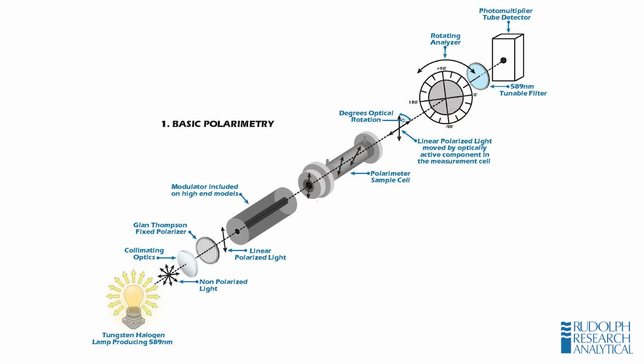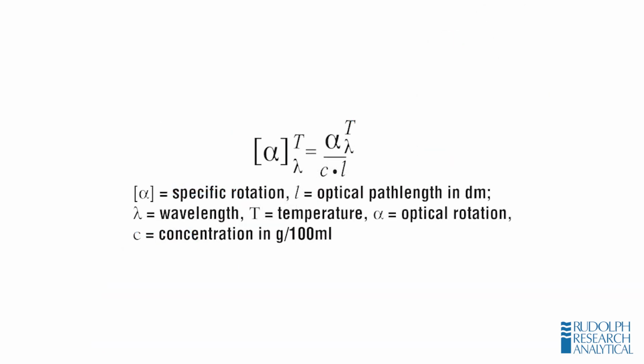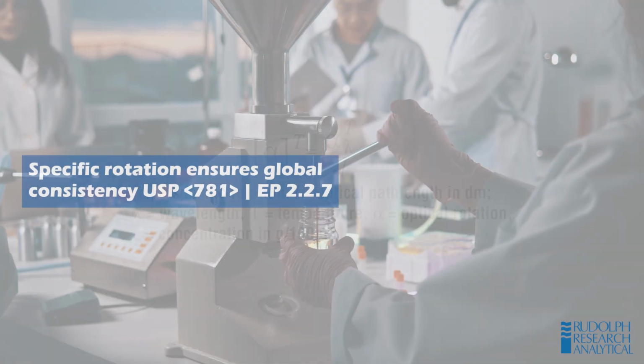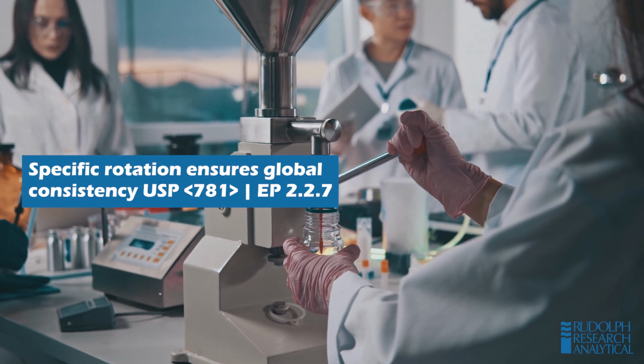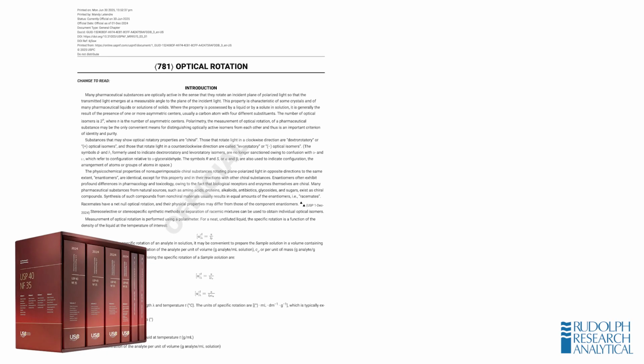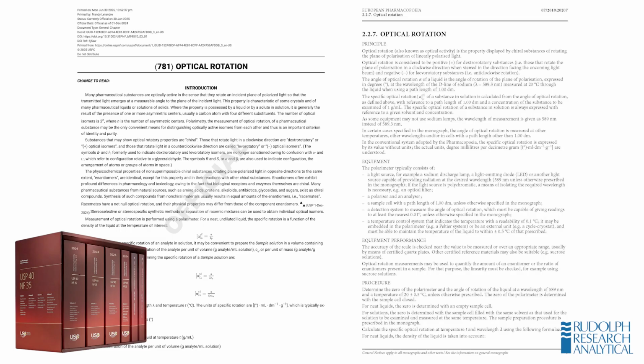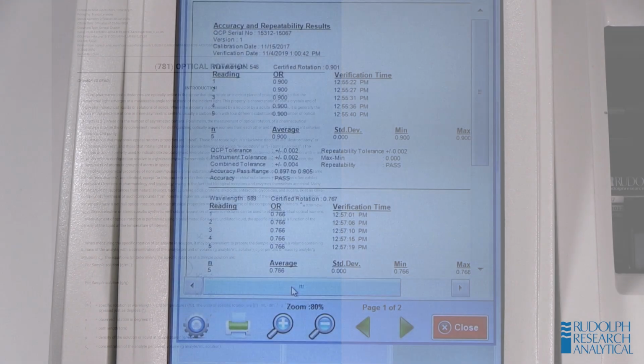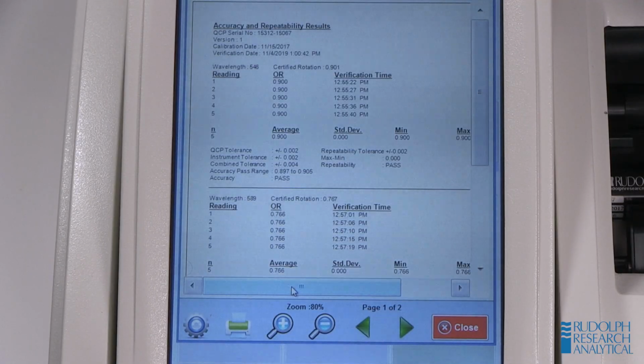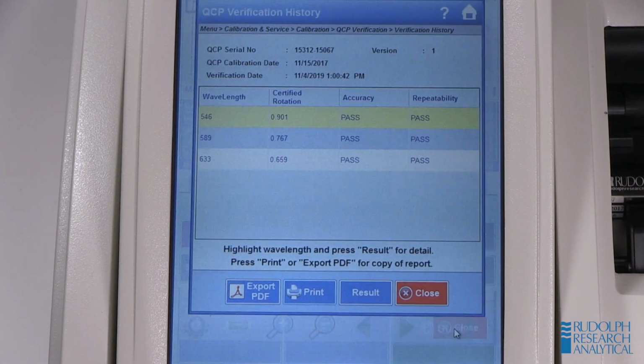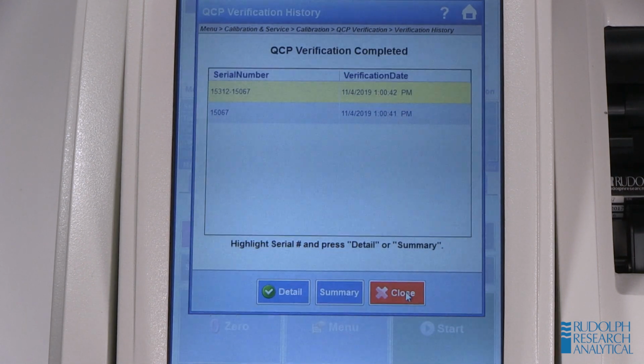A polarimeter measures optical rotation, the angle by which plane polarized light is rotated as it passes through an optically active sample. However, in pharmaceutical testing, what's actually reported and required is specific rotation, a calculated value that standardizes optical rotation for concentration, path length, temperature, and wavelength. Specific rotation allows laboratories to compare results globally, regardless of cell size or concentration. That's why pharmacopeal methods such as USP 781 and EP 2.2.7 require results to be reported as specific rotation. Rudolph polarimeters automatically calculate and display specific rotation once the user enters the sample concentrations and cell path length, ensuring accuracy, traceability, and full regulatory compliance.